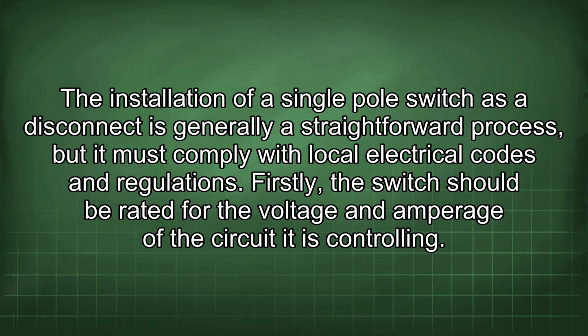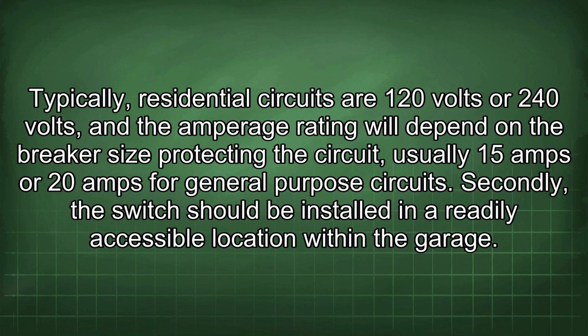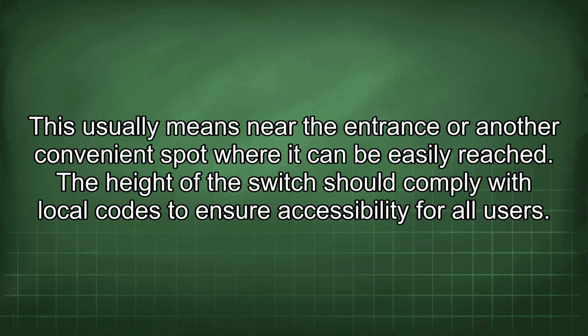electrical codes and regulations. Firstly, the switch should be rated for the voltage and amperage of the circuit it is controlling. Typically, residential circuits are 120 volts or 240 volts, and the amperage rating will depend on the breaker size protecting the circuit, usually 15 amps or 20 amps for general-purpose circuits. Secondly, the switch should be installed in a readily accessible location within the garage. This usually means near the entrance or another convenient spot where it can be easily reached. The height of the switch should comply with local codes to ensure accessibility for all users.